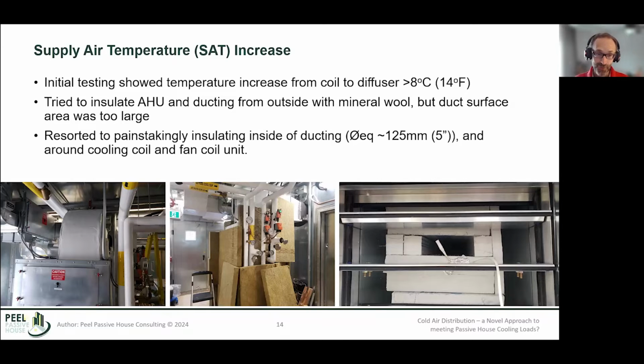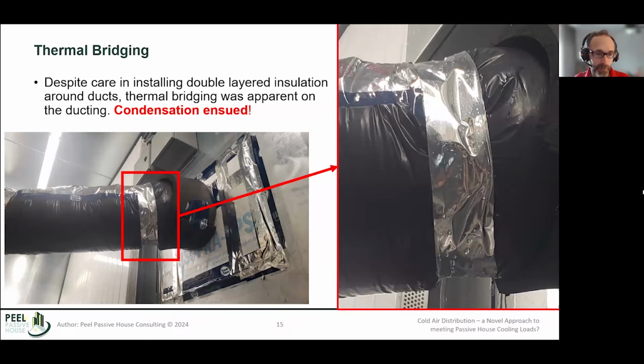So in the end, I resulted in painstakingly building an insulated duct within the existing duct, which gave me about a 5-inch equivalent diameter, as well as insulating all around the cooling coil and fan coil unit. That took a very long time, but in the end it worked, because towards the end of the experiments we actually managed to achieve under 36F at the diffuser, actually below what we were targeting, which is pretty amazing. So really stress tested the setup.